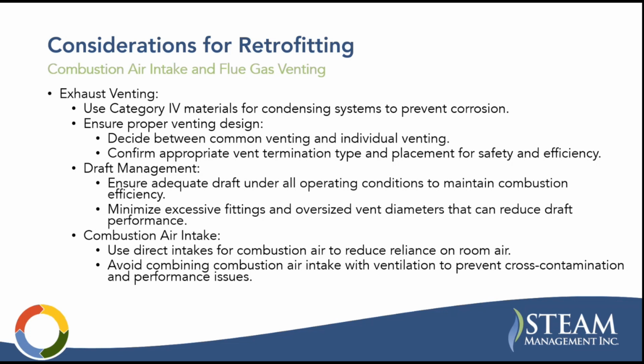And one of the reasons why is because this is wet flue gas, right? So if you're in a cold environment, you may have some ice buildup on the exit if you use something like a rain cap, and then you're constricting the rain cap even further and exacerbating the issue, and eventually having trips on your boiler and not operating correctly. So I got to definitely check the vent termination types on these. Make sure you're picking the recommended types, as well as considering anything that's affected by wind.